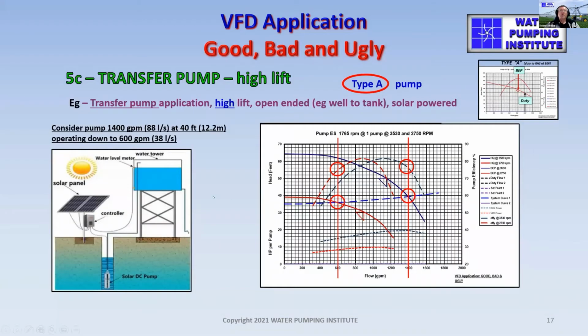What if we want to lift water a little bit higher, and this might be another solar application, for example, from a shallow well to a tank. So now you're starting to look at some lift. If you look at this curve here, the broken blue line is the system curve, and we might be starting off at 35 feet of lift. And if we use a type A pump, where the duty is to the right hand side of the best efficiency point, we will start off at this point where the efficiency is down to the right hand side.